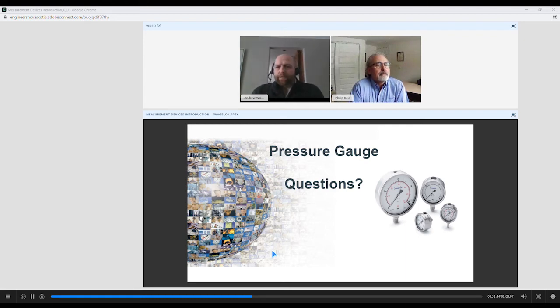Do the higher pressure gauges use helical tubes because the highest pressure applications require stronger and therefore stiffer materials? So there's a couple ways to look at this. Phil talked earlier about the calibration and the sensitivity of the Bourdon tube and working within a specific range. So the C-type Bourdon tubes are generally on the lower pressure ranges. With the helical types, you have much better sensitivity at the higher pressures, and they're a bit more robust. So it is a more robust solution for those higher pressures. So overall, you will see those helical tubes in the higher pressure gauges. Anything you want to add to that, Phil? No, that's good, Andrew.